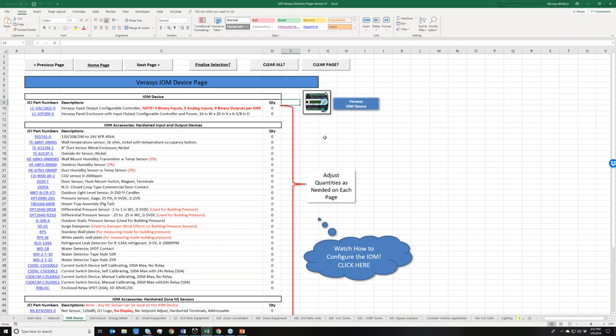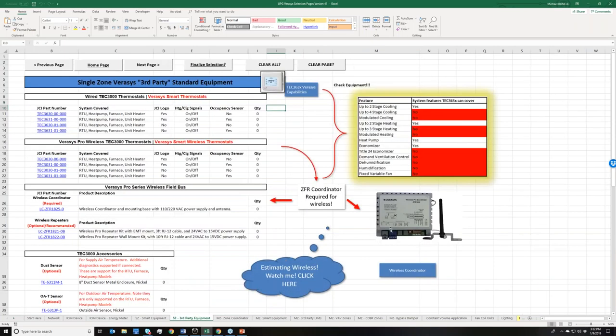But if you're talking about wireless TEC thermostats, that would be completely different, connected to this wireless coordinator. This wireless coordinator does not take the wireless sensors; all it does is wirelessly communicate through this antenna to the wireless thermostats. You have to set some addresses on both the wireless thermostat and the wireless coordinator, but it does not communicate with the wireless sensors I could use on the IOM most commonly.